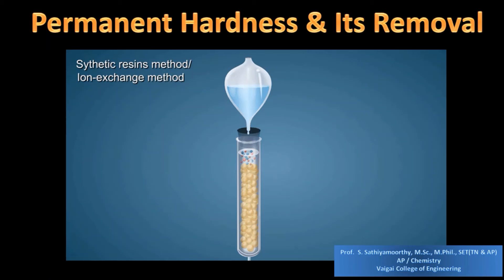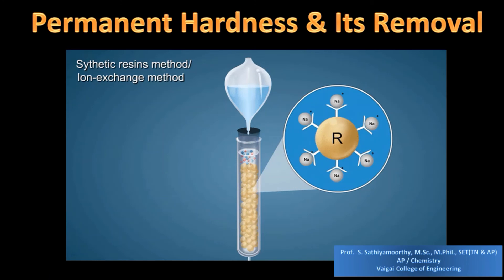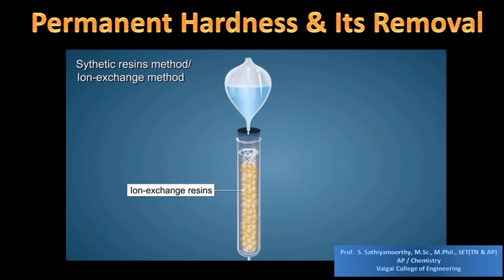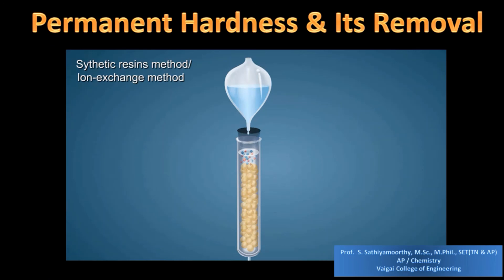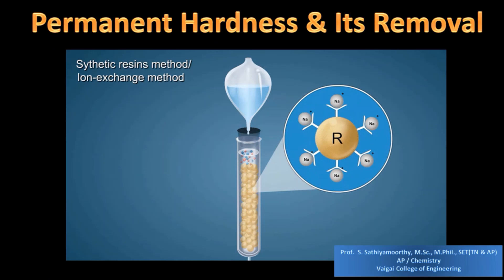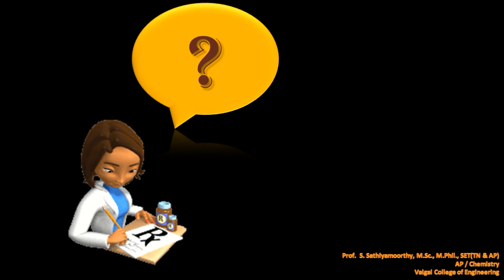Another method of removing permanent hardness is the synthetic resins method, also called the ion exchange method. The name itself describes everything — ion exchange resins are capable of exchanging their ions with the ions present in water. The harmful ions of water are exchanged by the ion exchange resins, which provide harmless ions to the water. Almost all the ions are removed, and finally what we get is deionized or demineralized water. By the ion exchange method, we can remove permanent hardness and also all ions present in the water.